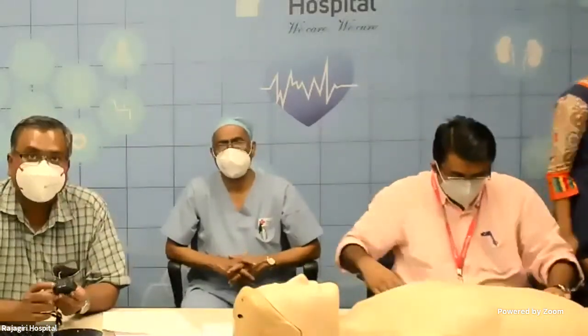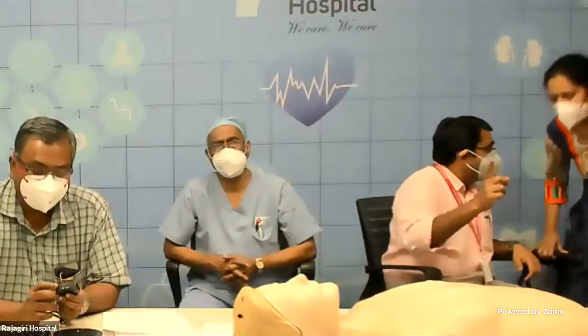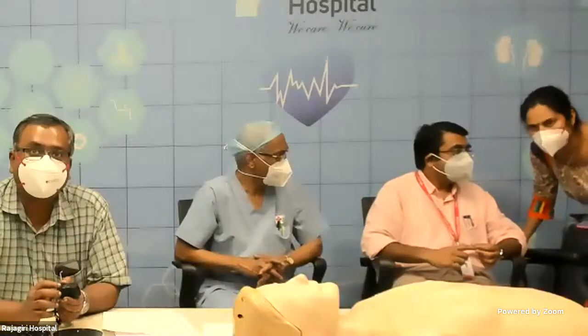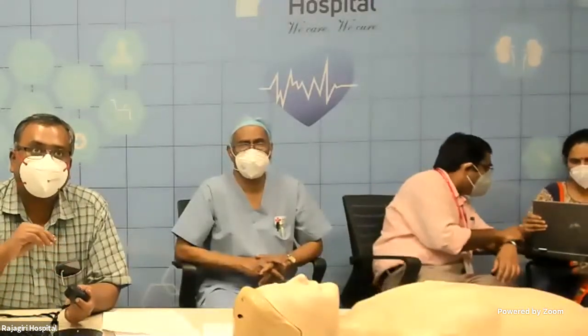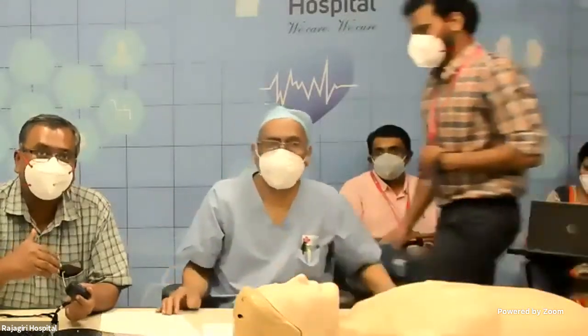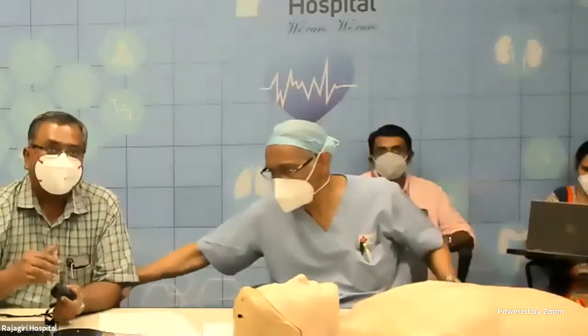So for this finger pulse oximeter, most of the time the correct reading does not come because you don't apply it in the right way. Every pulse oximeter will have a light source and a detector inside, and if the body tissue is not placed properly between the light source and the detector, the reading will not be proper. The light waves have to pass perpendicularly from the light source into the detector. If the light ray is passing in a tangential way, the reading will not be proper.